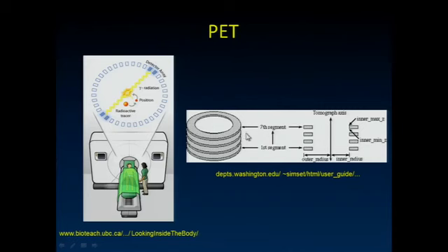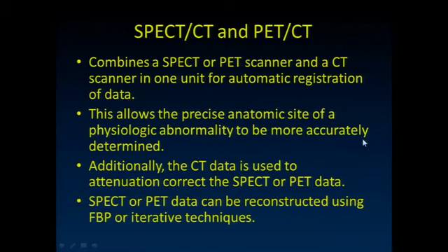Remember I mentioned that in the old PET scanners you would see collimators in there, and they were really in place so that you restricted to only be detecting events that were traveling in this direction and not so much detect events in this direction. In other words, we operated the old PET scanners in 2D mode where they were detecting, if you will, events occurring in a single slice and not allowing 3D detection of events. That has really kind of changed.